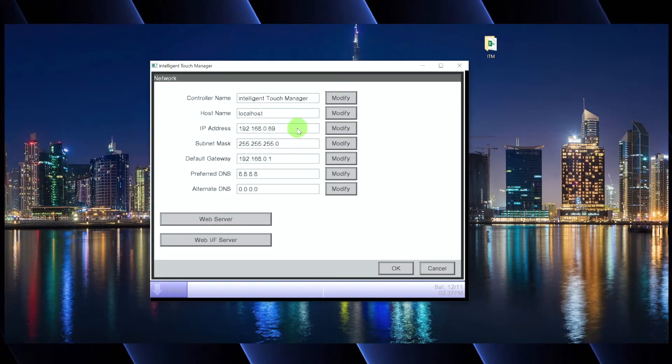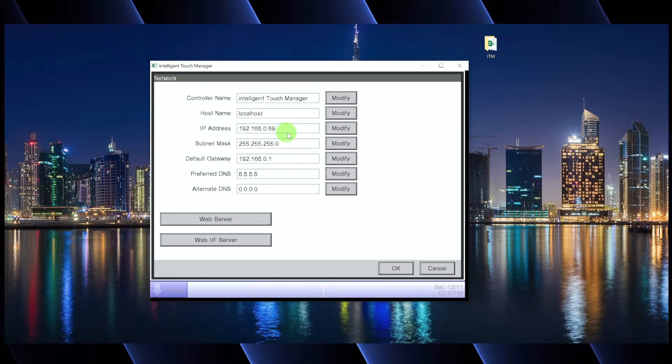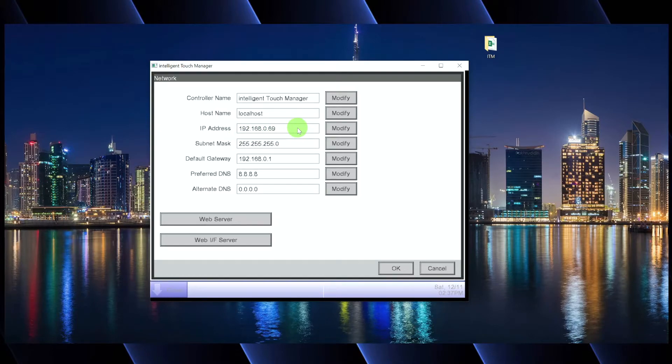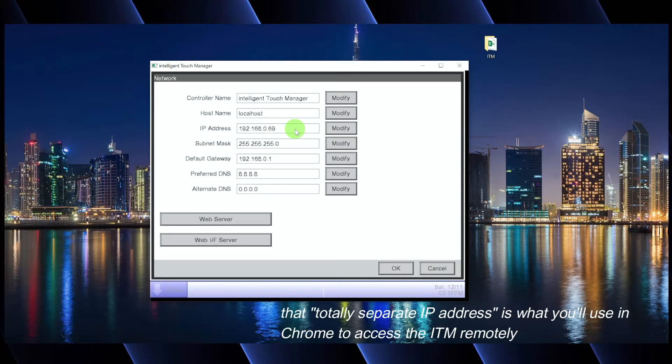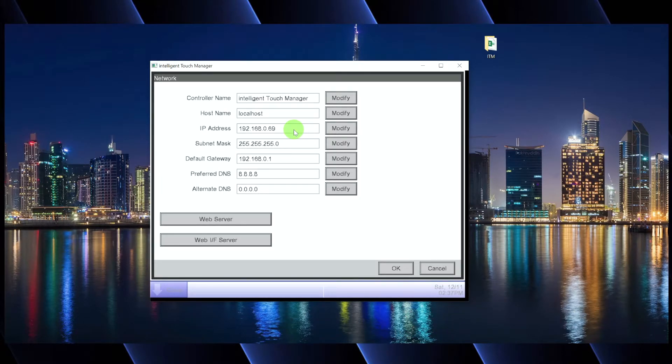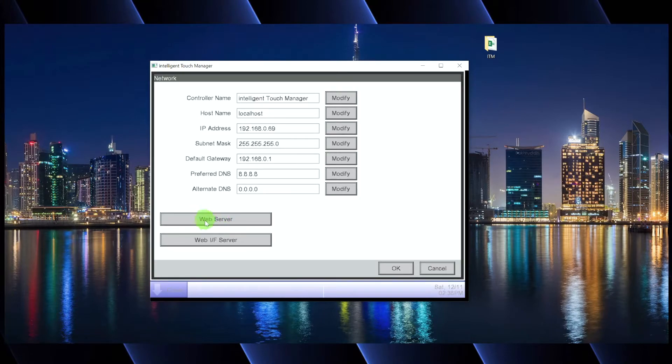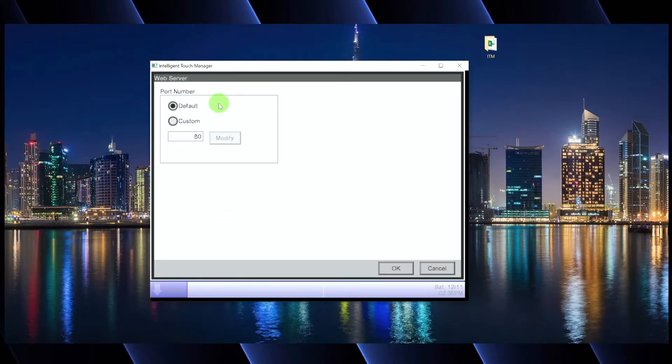Now, for remote access purposes, typically what's going to happen on a building network is the ITM will have this IP address, but the IT person is actually going to forward this port somewhere else onto the internet. And then they're going to give you a totally separate IP address. And it's that separate IP address that you're going to use in Google Chrome or your Explorer tab to actually access the ITM. You dial it up and you're going to dial it up with a particular port number.